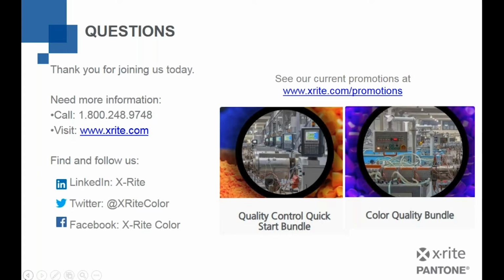But the spectrophotometer sees everything that light can interact with and come back to the sensors, and so that includes the substrate. Sometimes it's an unintentional substrate. I say that because you might be measuring something, let's say it's a piece of plastic that's not opaque. If you're measuring that with a handheld instrument and you lay it on your desk and take a measurement of it, you just measured your desk as well as the plastic, and so your measurement that the instrument just detected is a combination of those things. Were you to take that plastic and lay it on top of something different, you'll get a different answer. So substrate always makes up part of what is being measured.